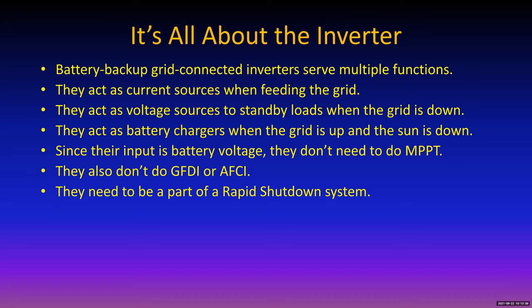And they also need to be a part of a rapid shutdown system since, when was it, 2014? I guess rapid shutdown came in, and it was one of the first times that the requirement of NEC was not prescriptive, but it was performance type. You shut it down and we don't care how you do it if there's an emergency. So the inverter has to be one of the players in that.